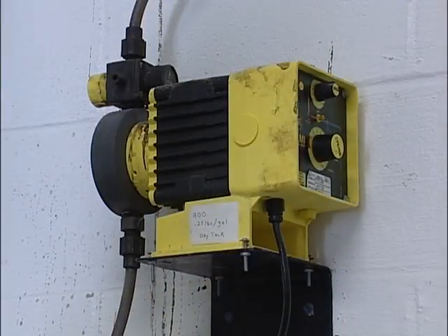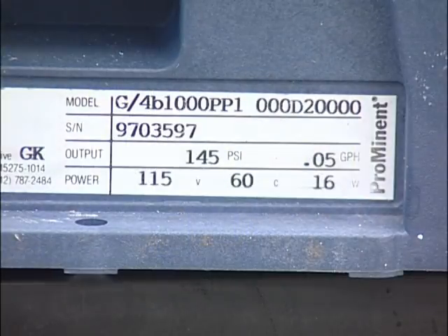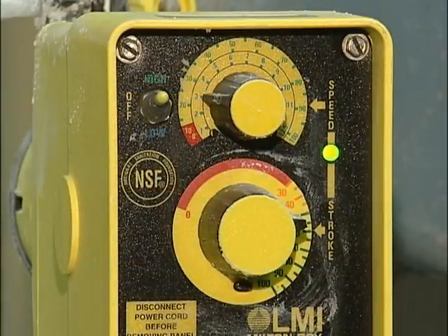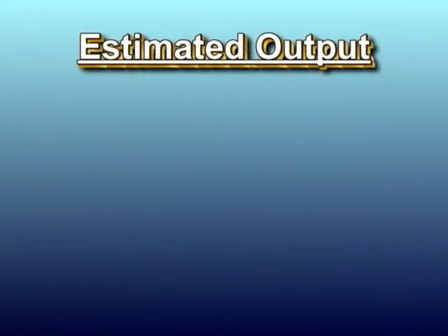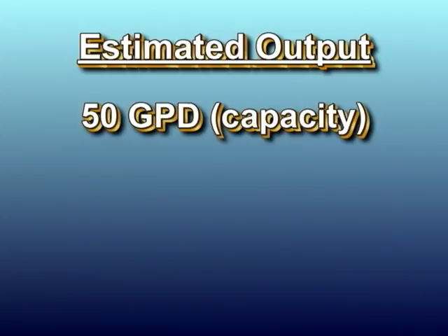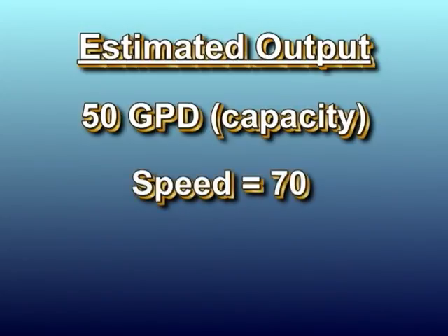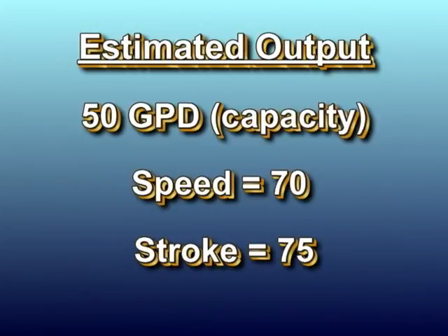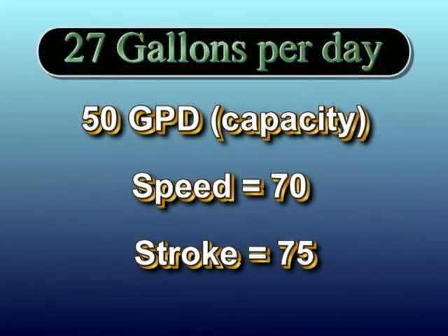Assuming that you have purchased the right pump for the job does not mean that you can just plug it in and watch it work. Some pump manufacturers suggest that the output of a pump can be estimated by multiplying the rated capacity of the pump by the speed setting and the stroke setting. For example, if a pump is rated at 50 gallons per day maximum, and the speed is set at 70, and the stroke is set at 75, the pump should be delivering about 27 gallons a day.